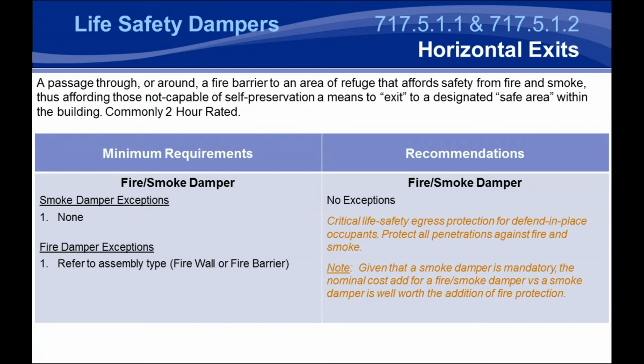Because of that, the minimum and the recommended requirements are a fire smoke damper without exception. Now, of course, there are different exceptions based on the assembly type. So if it's a firewall or a fire barrier, you can use the exceptions of those different assembly types. But we definitely recommend a fire smoke damper because at the minimum, it's going to add a little bit of additional cost, but you'll need that smoke damper no matter what. And you'll get the additional protection of the fire damper, making sure there's no degradation of this barrier that can let smoke around the opening as opposed to through the ductwork.